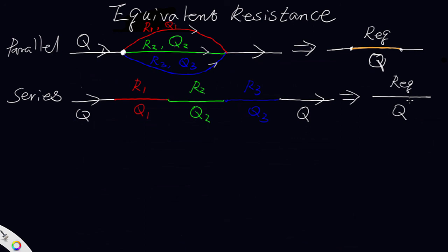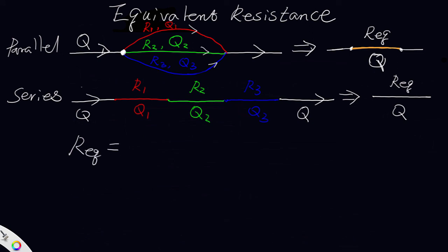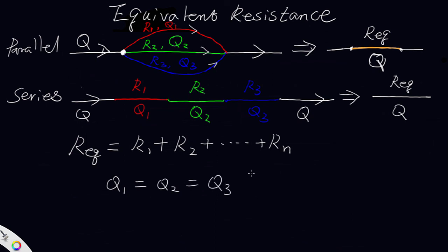It is important to know the equivalent resistance and quantity because we need the pressure drop in that airway or series of airways: P equals R times Q squared. For airways in series, the equivalent resistance equals R1 plus R2 plus ... plus Rn, and all flow quantities are equal: Q1 equals Q2 equals Q3 equals Qn equals Q.